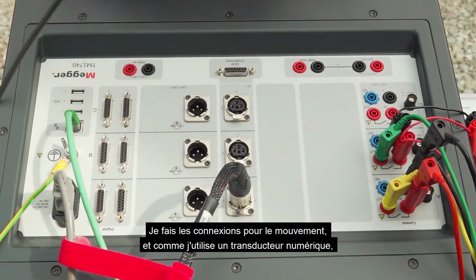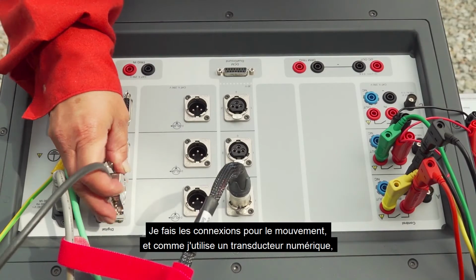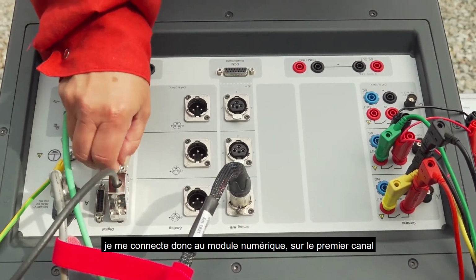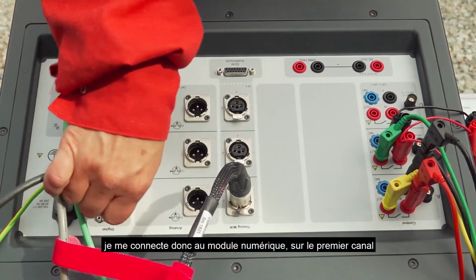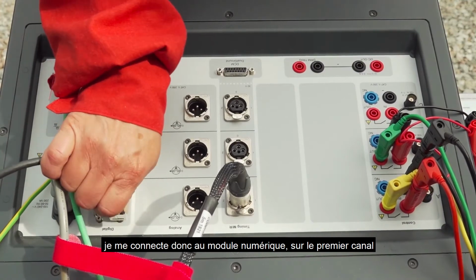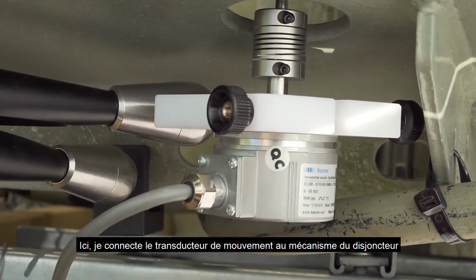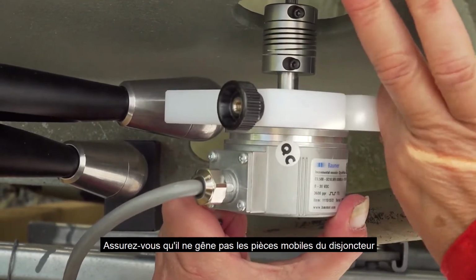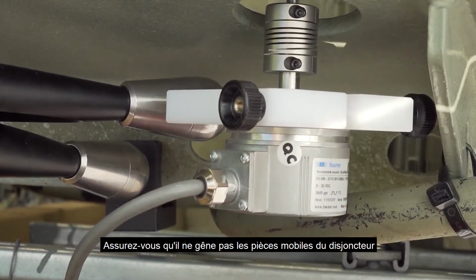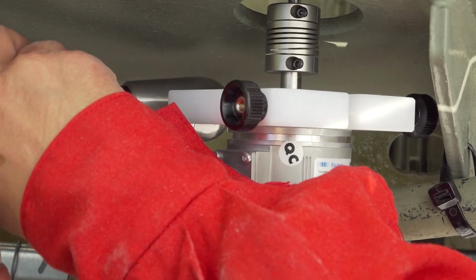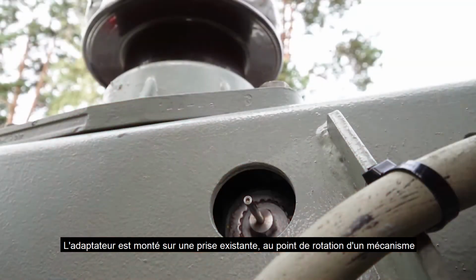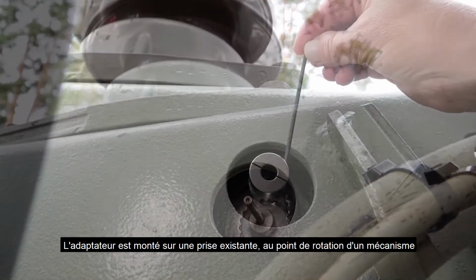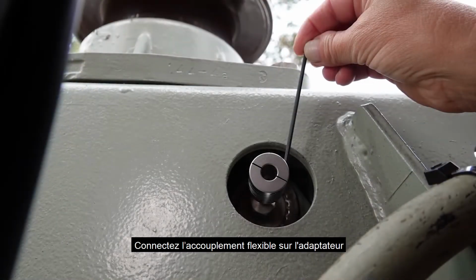I do the connections for the motion, and I'm using the digital transducer, so I'm connecting to the digital module, the first channel. Here I connect the motion transducer at the circuit breaker mechanism. Make sure it's not in the way of the moving parts of a circuit breaker. The adapter is mounted in an existing drilled hole in the rotating point of the mechanism. Connect flex coupler to adapter.